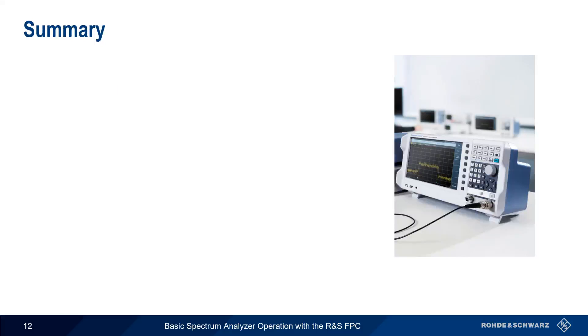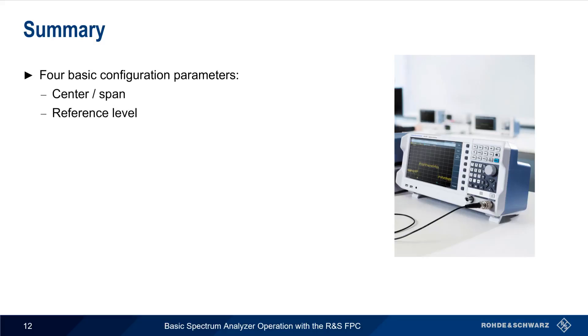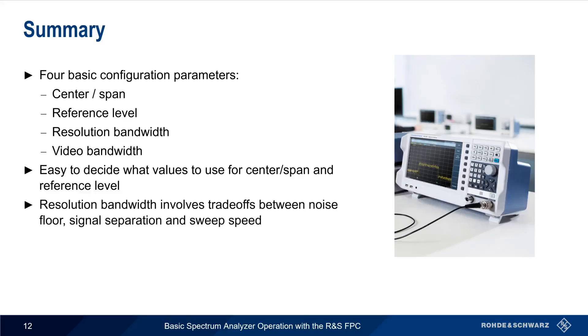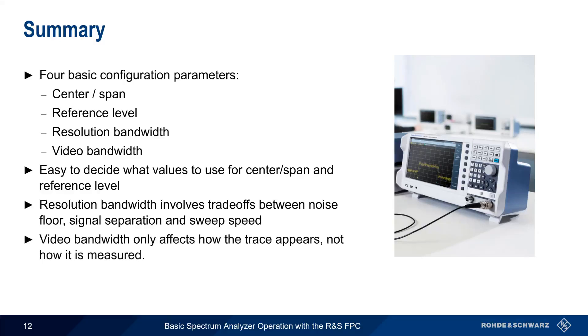In this presentation, we've introduced you to the four most important configuration parameters when using the FPC: center and span, reference level, resolution bandwidth, and video bandwidth. For center, span, and reference level, it's not very hard to decide what values to use. Resolution bandwidth, on the other hand, involves trade-offs between noise floor, signal separation, and sweep speed, so the best resolution bandwidth setting will depend on the application or measurement task. And we saw how video bandwidth affects the appearance of a trace, but doesn't affect how that trace is measured.